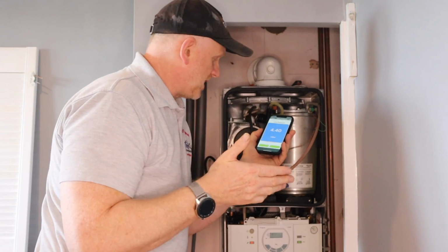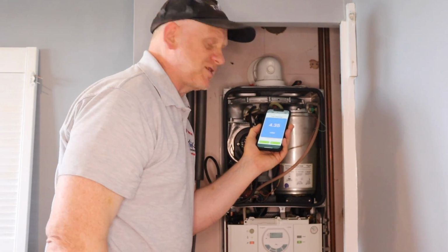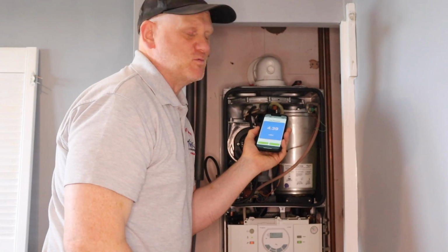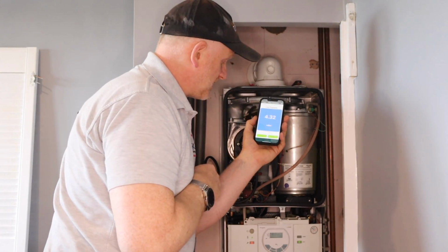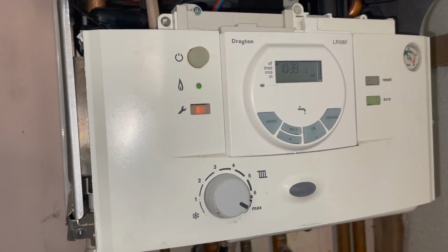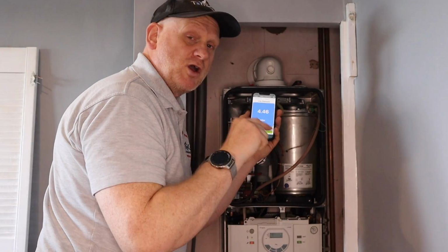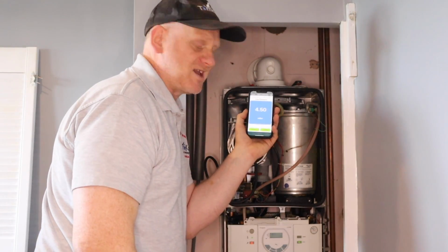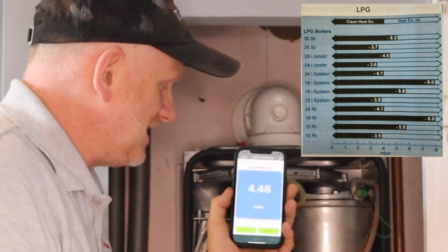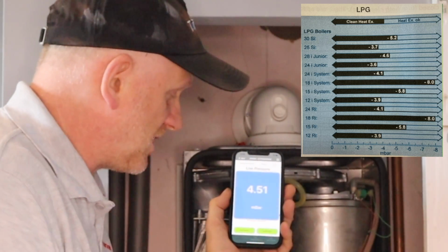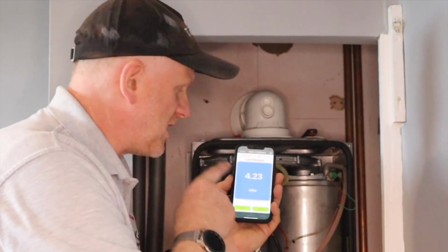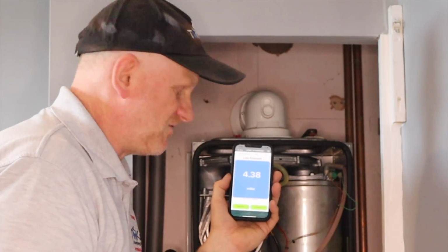So now I've got it built back up again, I'm just going to test the inlet pressures and see if it's made any difference. I guess it won't. So I've got my TPI app here with my TPI digital manometer. I've connected it back onto the test point. I've put the boiler in maximum rate, and remember we need to be higher than minus 4.6. So I've got this on the minus setting on the actual digital manometer, and you can see it's still the same. So we're on 4.5, just lower than the 4.6. So we need to get those baffles out and give it a good service and a good clean.